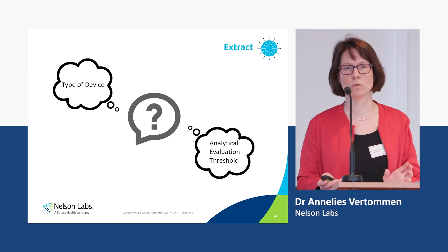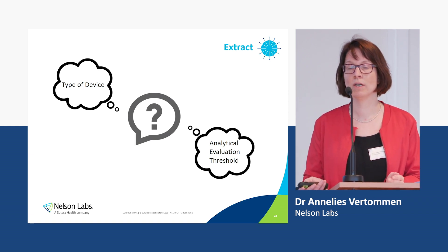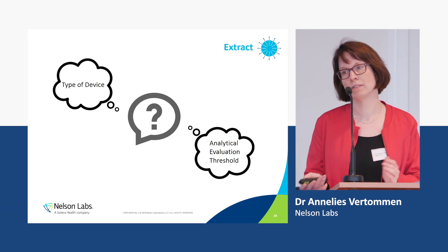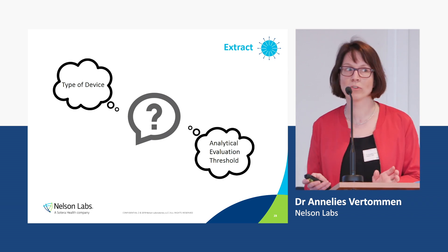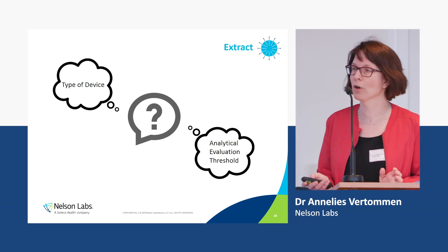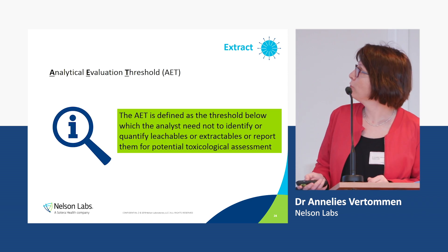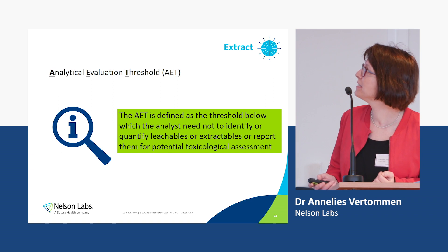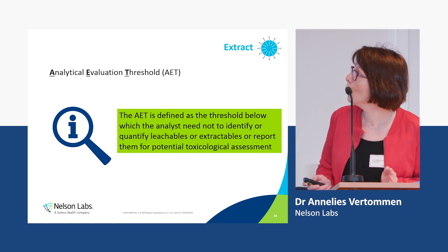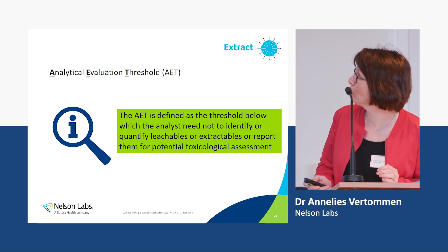There are two main questions we ask when a customer comes to us and we need to set up a chemical characterization study. First, we look at the type of the device. Second, what will be the analytical evaluation threshold to be used? The analytical evaluation threshold — the AET — is a new concept. It's defined as the threshold below which the analyst need not identify or quantify leachables or extractables, or report them for potential toxicological assessment.